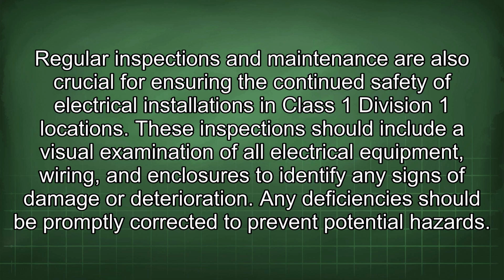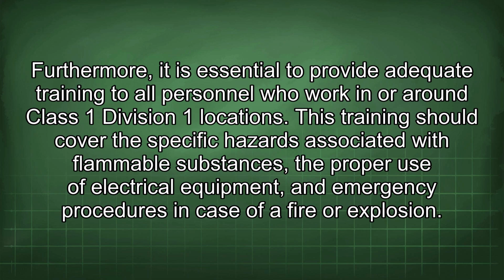These inspections should include a visual examination of all electrical equipment, wiring, and enclosures to identify any signs of damage or deterioration. Any deficiencies should be promptly corrected to prevent potential hazards. Furthermore, it is essential to provide adequate training to all personnel who work in or around Class 1 Division 1 locations. This training should cover the specific hazards associated with flammable substances, the proper use of electrical equipment, and emergency procedures in case of a fire or explosion.